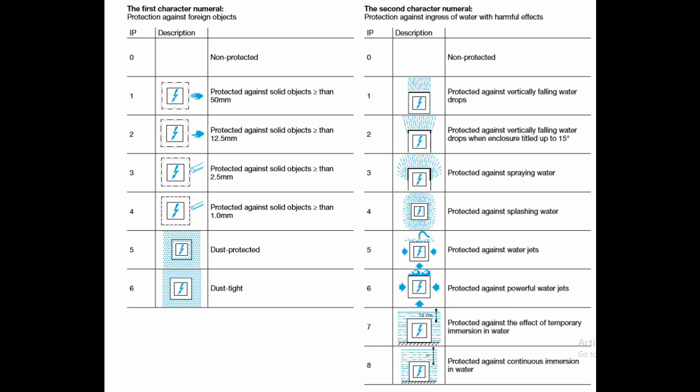If it is 1 for the first term, it is protected for solid objects greater than 50mm. If it is 2, solid objects greater than or equal to 12.5mm. If it is 3, solid objects greater than or equal to 2.5mm. If it is 4, greater than or equal to 1mm. If it is 5, it is dust protected. If it is 6, it is dust tight.